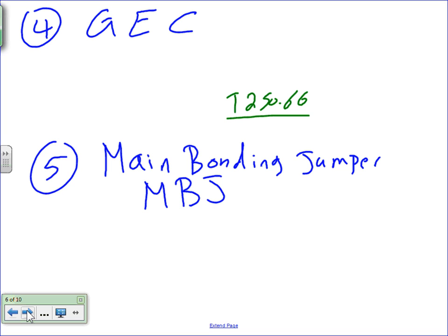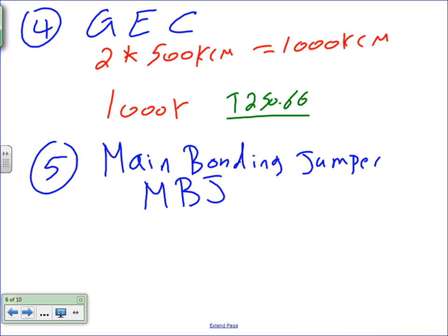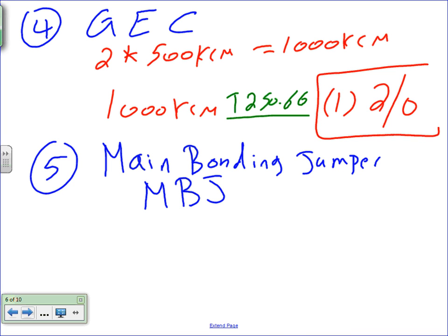Okay, grounding electrode conductor, 250.66. Grounding electrode conductor, guys, if you parallel, the code says you have to multiply your 2 sets. When you parallel 2 sets, multiply them by 500, not 5,000 like I did. 500 kcmil, and that will get you a healthy 1,000 kcmil. You take your 1,000 kcmil to table 250.66. And you end up with only one solo conductor, 2/0. One 2/0 conductor, only one. That's number 4, the one that's going through the steel of the building. Any questions, guys, about this?